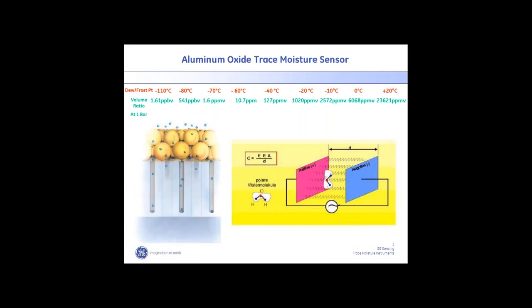The sensor has a very wide dynamic range. It covers a dew point measurement from negative 110°C to plus 20°C dew point. If we convert that dew point at atmospheric pressure to a volume ratio in parts per million by volume — where one part per million means one water molecule for every million surrounding gas molecules — that range covers about 1.61 parts per billion to about 24,000 parts per million by volume. That's a full ratio the sensor covers of almost 15 million, essentially a turndown ratio of about 15 million.